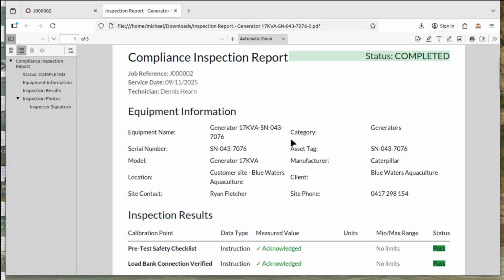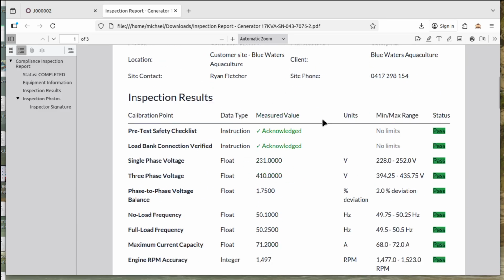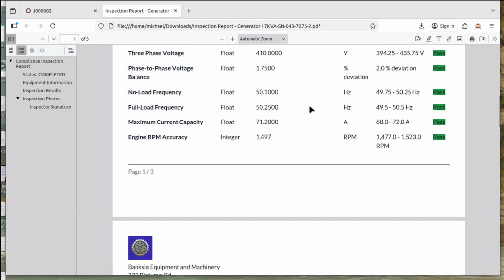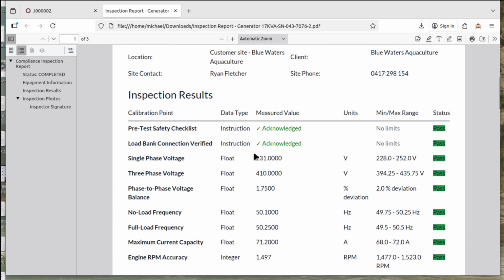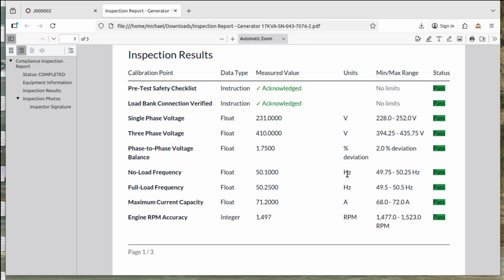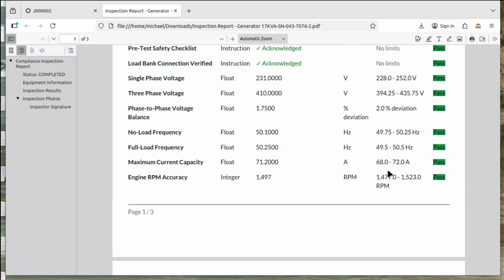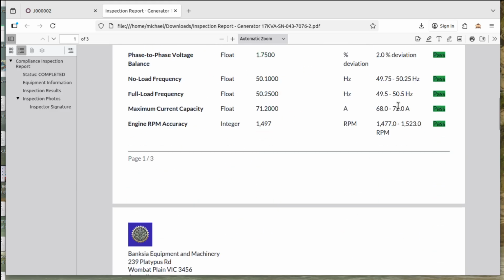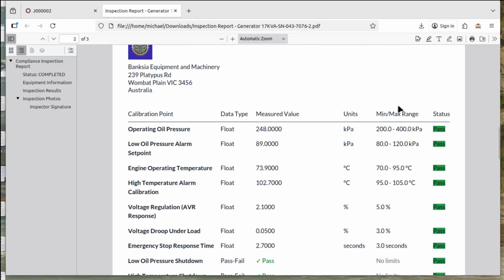At the top here we've got some information about the unit itself, and then I can go into the results down here, and I can see all of the values that we measured against the values that they should have been, the range in between that they were tested against. Now during the test, the operators don't see the minimum and maximum, so they can't fudge the numbers. They've got to put in the actual numbers, otherwise they may, as I say, try and sneak away with getting the calibration done without actually doing the measurement. So we do not include the mins and maxes in that display. We'll have a look at that a little bit later.